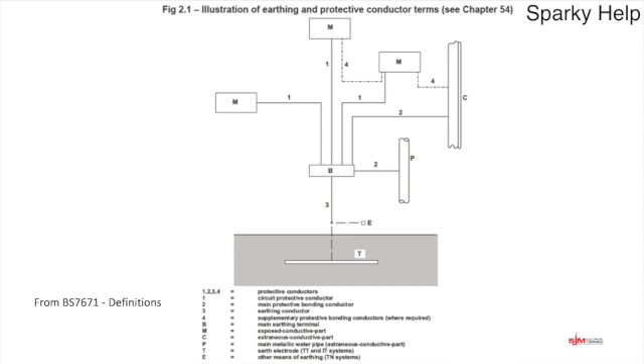Number 1, the most common one that you will probably see up there, is your CPCs, the circuit protective conductors, which obviously go with your lights, your sockets, your power, or whatever else it is you're running out, and that is one of the things that we will look at sizing. Number 2, another very common conductor, is your main protective bonding conductors, your main equipotential bonding, which goes to your water, your gas, your structural steel, your lightning protection maybe, or any other type of extraneous conductive part. Another one up there is number 4, which is the dotted line, the supplementary protective bonding conductors, as it's got in brackets, where required. So we'll look at the sizing for those, for if anyone out there still does it.